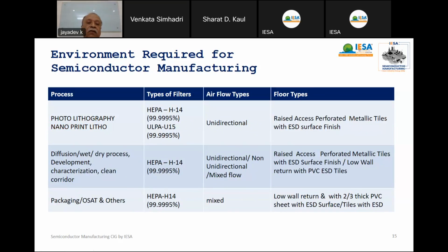Apart from that, let us discuss the types of filters we are going to use, the airflow pattern, and the types of floor we use for the clean room. For photolitho and nanoprinting, this may be a class 100 clean room. For class 100, normally we use HEPA filters H14, 99.9995% down to 0.3 micron particles. And for ISO 4, we use ultra low penetration air filters, called U15, 99.9995% down to 0.12 microns. Here it is 0.3 microns, 0.12 microns.